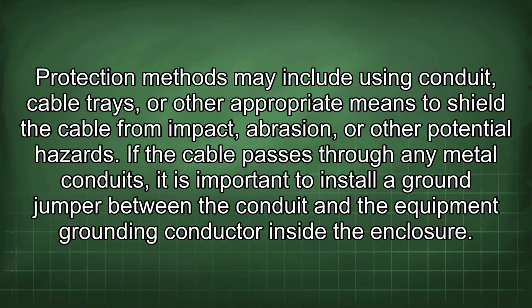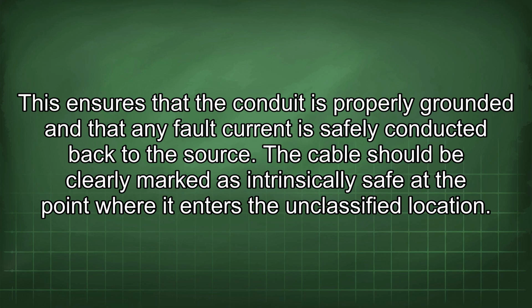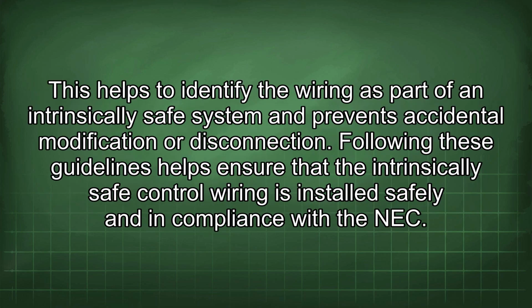Protection methods may include using conduit, cable trays, or other appropriate means to shield the cable from impact, abrasion, or other potential hazards. If the cable passes through any metal conduits, it is important to install a ground jumper between the conduit and the equipment grounding conductor inside the enclosure. This ensures that the conduit is properly grounded and that any fault current is safely conducted back to the source. The cable should be clearly marked as intrinsically safe at the point where it enters the unclassified location. This helps to identify the wiring as part of an intrinsically safe system and prevents accidental modification or disconnection.